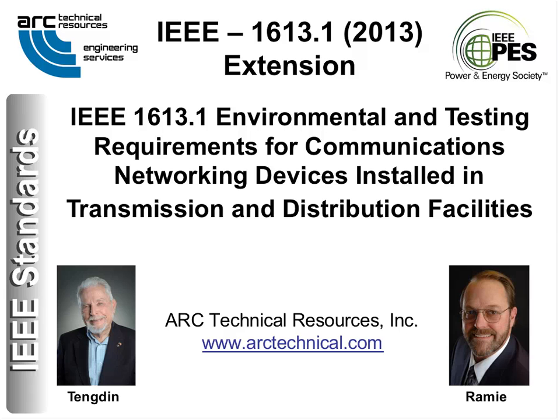Then Michael asks, would the new set of standards replace the incumbent NEBS, the Network Equipment Building System? No, NEBS, or the Network Equipment Building Specification, is for telecom equipment only. If you're selling central office equipment that's powered on minus 48 volts and goes into a telephone company's central office, that's NEBS tested. It doesn't have really anything to do with what utility equipment that goes into transmission or distribution facilities is tested to. And if I recall, NEBS also has a set of requirements for physical durability. Yes. Which this does not cover.